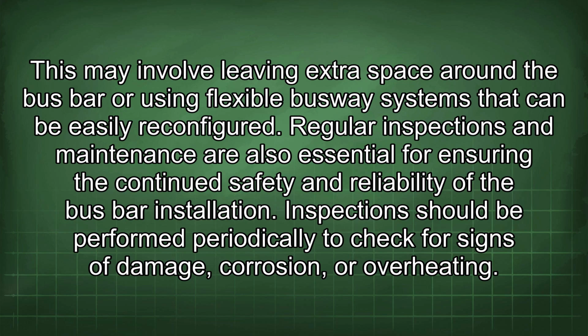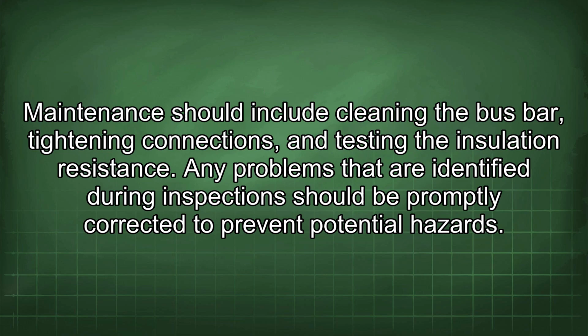Regular inspections and maintenance are also essential for ensuring the continued safety and reliability of the bus bar installation. Inspections should be performed periodically to check for signs of damage, corrosion, or overheating. Maintenance should include cleaning the bus bar, tightening connections, and testing the insulation resistance. Any problems that are identified during inspections should be promptly corrected to prevent potential hazards.